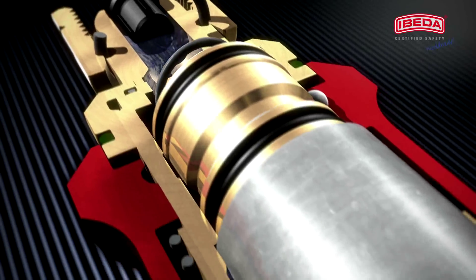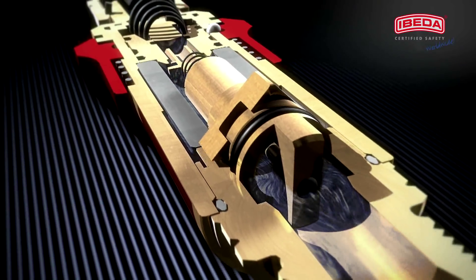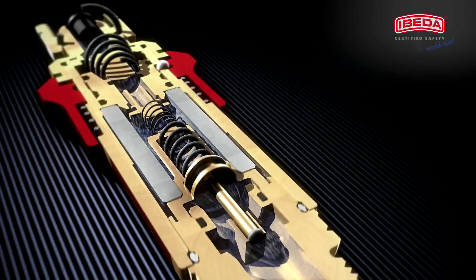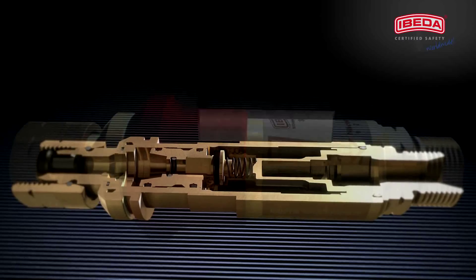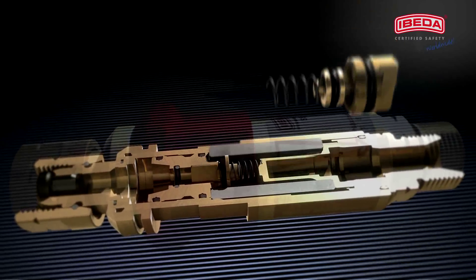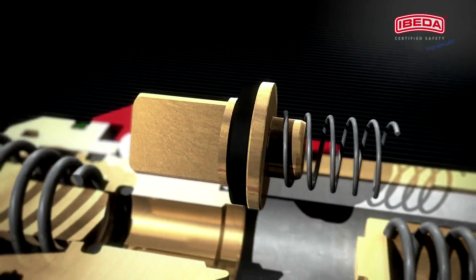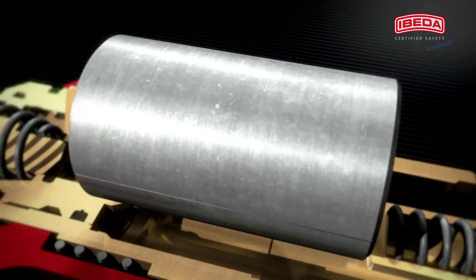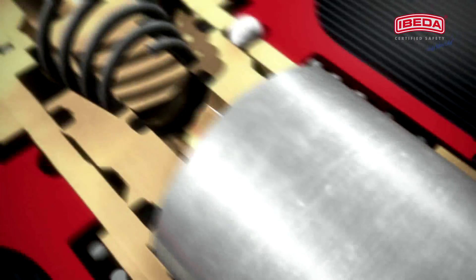IBEDA safety devices containing multiple functions conform to international standards EN-730 part 1 and ISO 5175, and are equipped with at least two and as many as four safety features: a gas non-return valve, a flame arrester, a thermal cutoff valve, and a pressure sensitive cutoff valve.